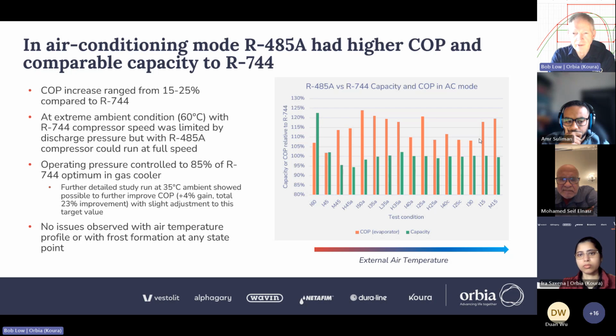But at the left-hand end, the extreme temperature end, you can see, for example, at 60C point, it has a much higher capacity than CO2. That is actually because the protective systems in the compressor wouldn't let it run at full speed with CO2 for 60C. The discharge pressure was over 125 bars and the discharge temperature was over 170C, and the system's inbuilt cutouts wouldn't let it run at full speed. Whereas the blend running much lower pressure was able to maintain full capacity, and hence the large disparity in apparent capacity.